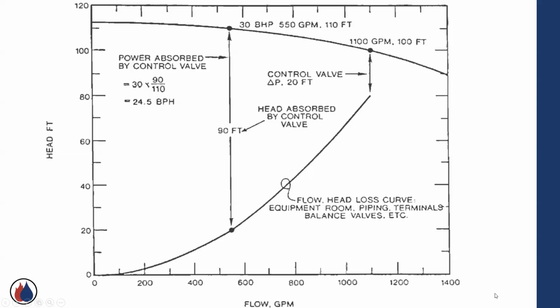It backs up on its curve because there are fewer ports, fewer terminals open. What happens at the control valve is you're developing this high head, and all of a sudden this valve's responsible for eating up that really excessive pressure drop. In this case, at about 50%, 550 gallons a minute instead of the original design of 1,100, the head absorbed by the control valve might be as much as 90 feet. Very excessive.